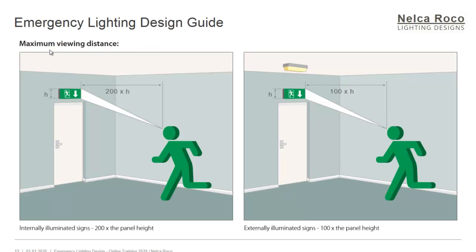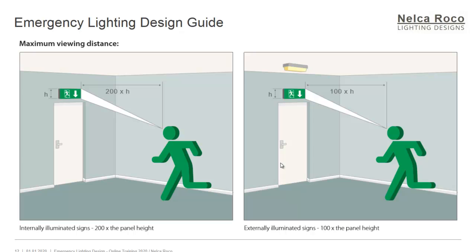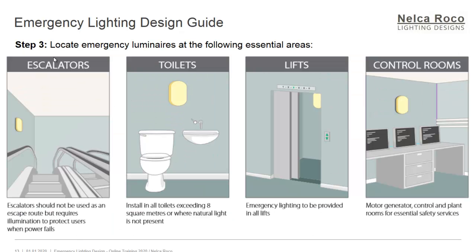Aside from the images for the exit sign, you should also consider the maximum viewing distance of the fitting. For example, if it is an internally illuminated sign, it should be visible from 200 meters. If it is externally illuminated, it should be visible from 100 meters.